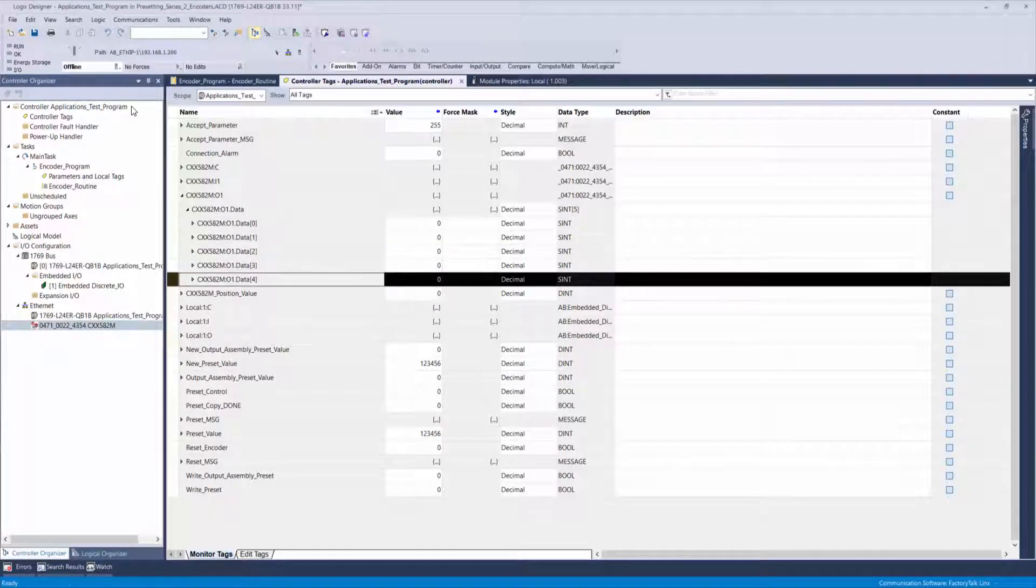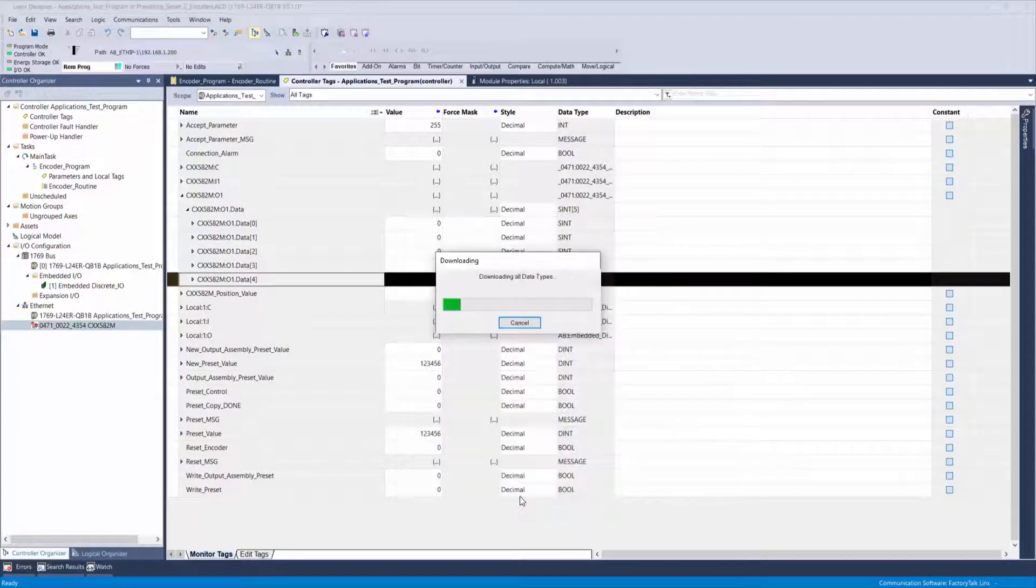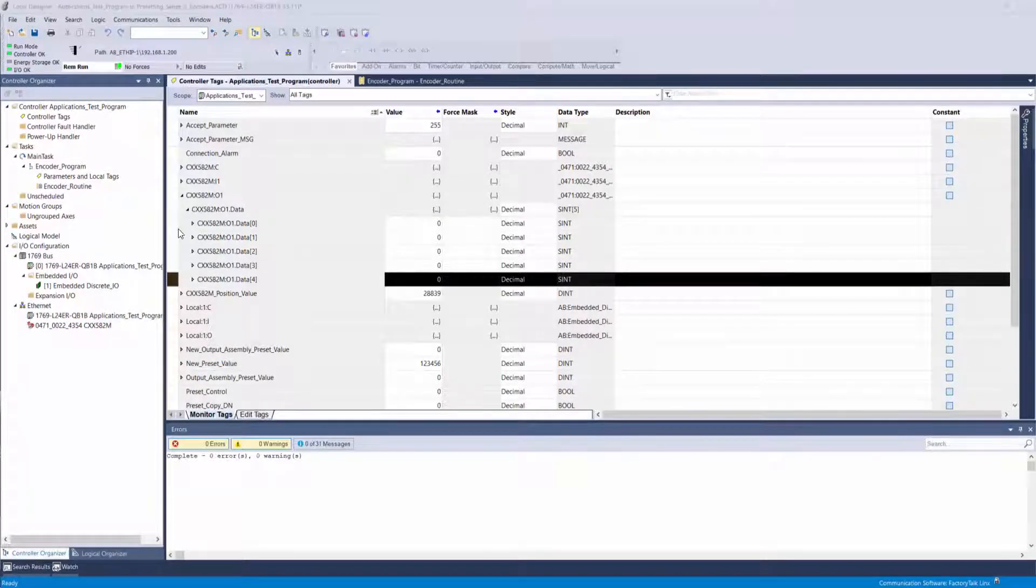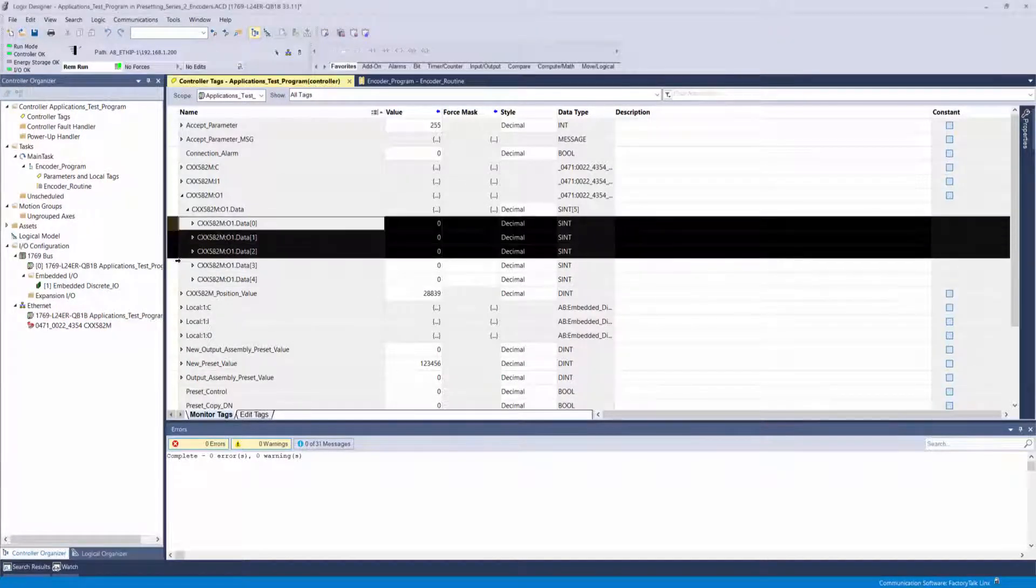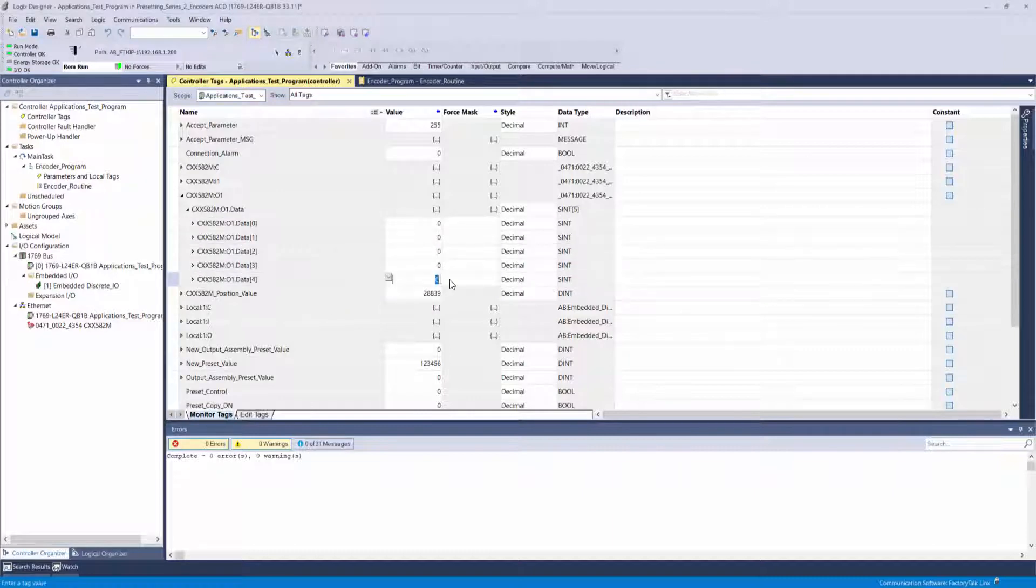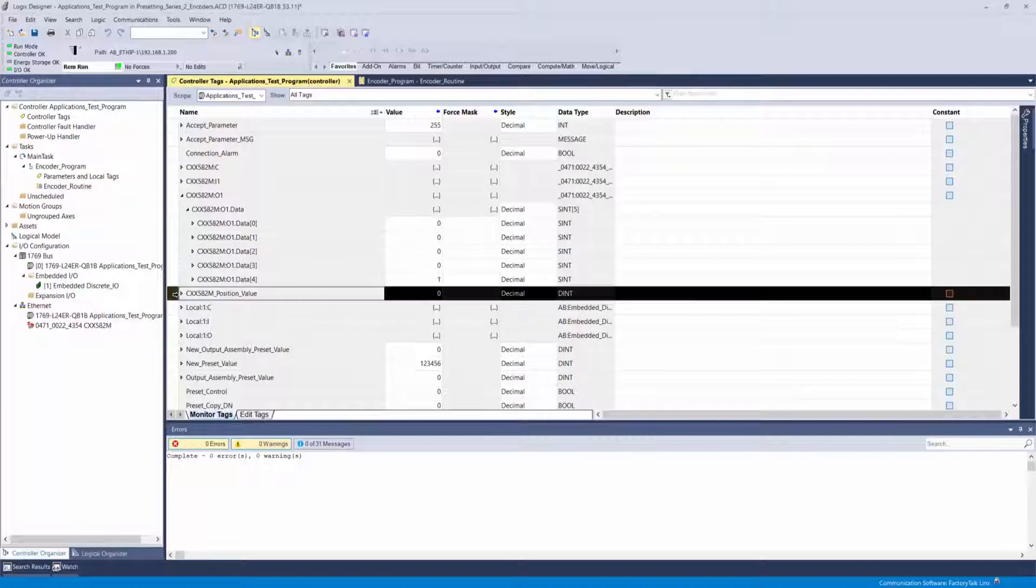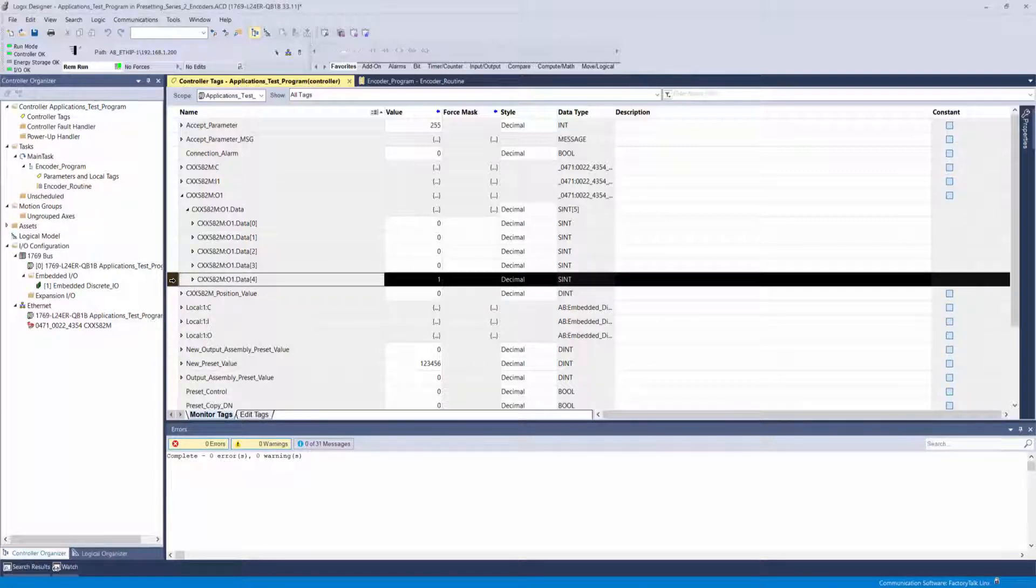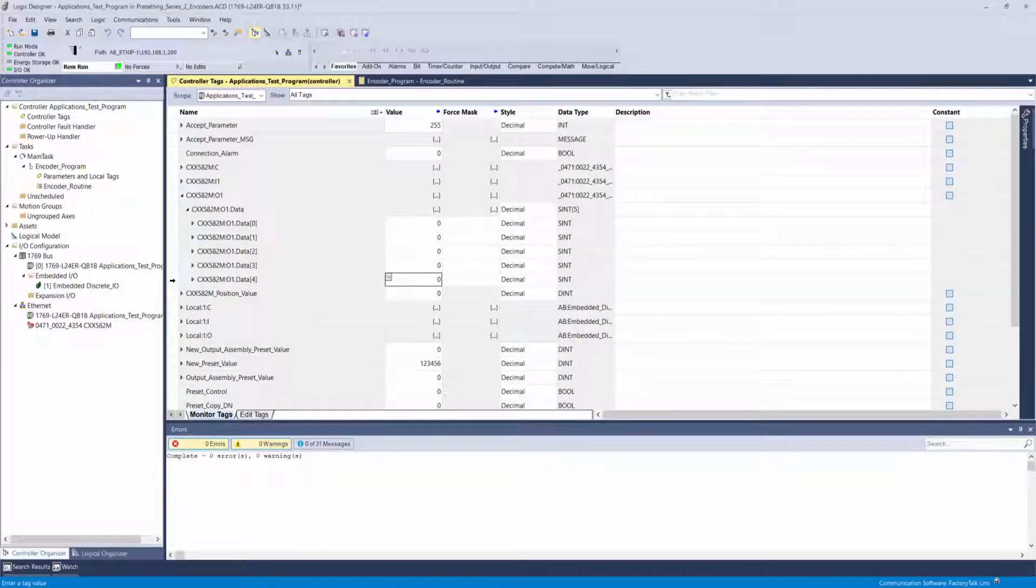Download and go online with the controller again and go back to your output assembly in controller tags. Leave the first four bytes as zero values, then define byte 4 as a value of 1. The moment you hit enter, the position value will change to 0 and you can verify your input assembly data is now showing a position value of 0. Then go back and set the tag value of byte 4 to 0 again.